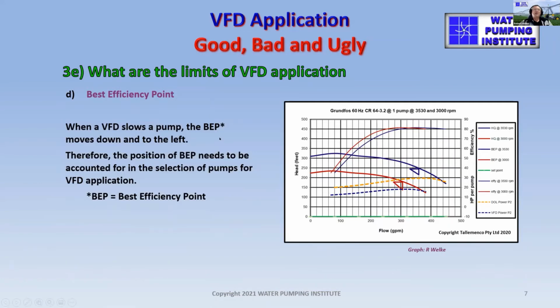Let's talk about best efficiency. When a VFD slows the pump, the best efficiency point moves down and to the left. And you can see here, and similar, I demonstrated that with the software when we started. So this blue line is a full speed, otherwise known as direct online. And when we slow the pump down, it moves off to the left, the BEP.